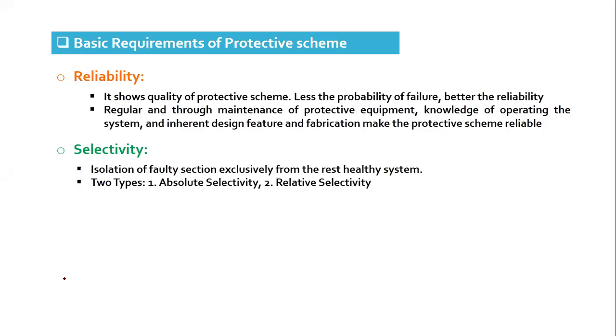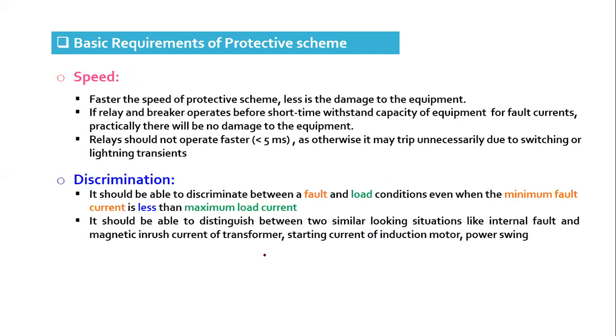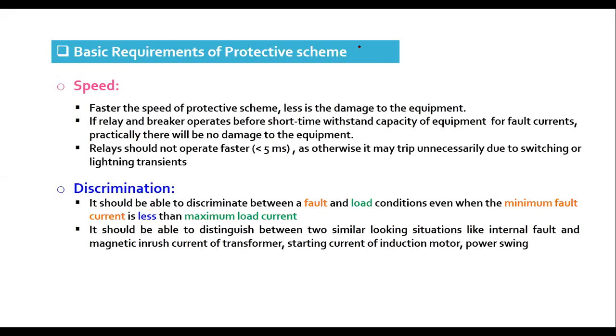Then comes selectivity, which is to select only the faulty part and isolate it from the rest of the healthy system. There are two types of selectivity based on the protection scheme: absolute and relative. Speed: the higher the speed of operation, the lesser the damage, obviously. But the speed should not be so high that it doesn't utilize the equipment's short time withstand capability. Sometimes we do not require fast tripping, as the system can withstand the situation for some period of time. Also, speed less than a quarter cycle after the inception of the fault is not advisable, because then it may unnecessarily trip during the transients.